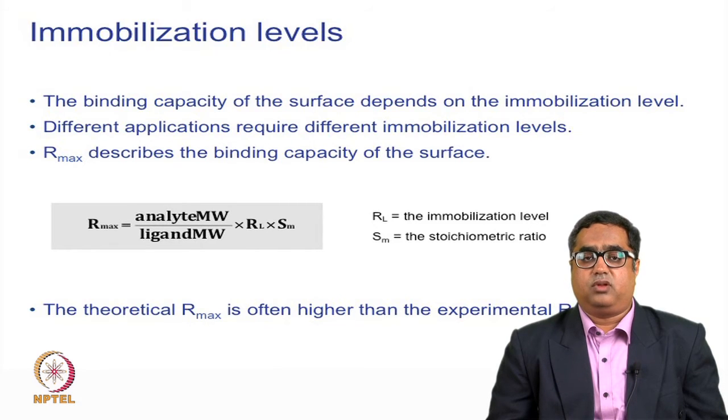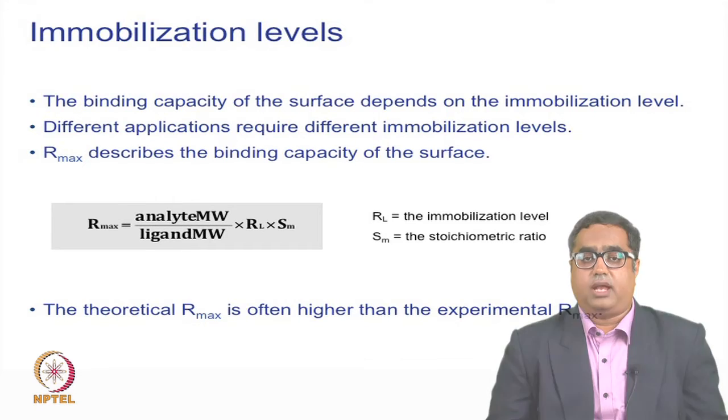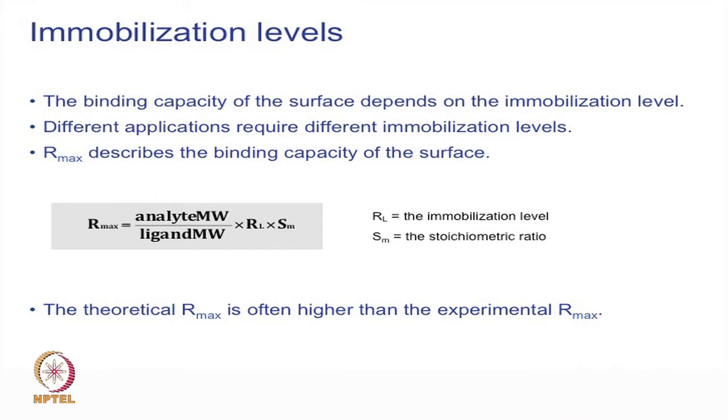Once the immobilization level is determined, we ask the machine to immobilize at that particular level. Alternatively, we can use time and flow mode, where the molecule is flowed at a particular pH for a set amount of time at a particular flow rate, and whatever immobilization occurs at the end becomes the immobilization level.